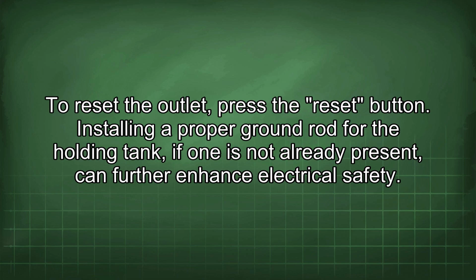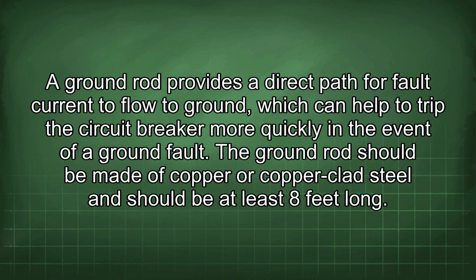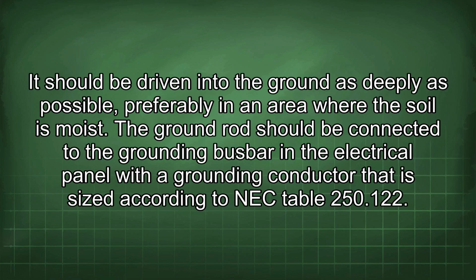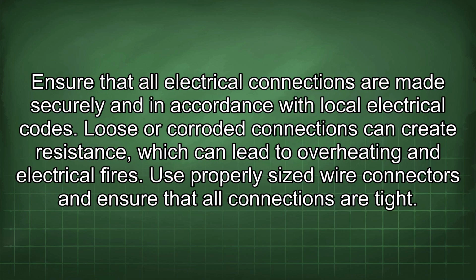Installing a proper ground rod for the holding tank, if one is not already present, can further enhance electrical safety. A ground rod provides a direct path for fault current to flow to ground, which can help to trip the circuit breaker more quickly in the event of a ground fault. The ground rod should be made of copper or copper-clad steel and should be at least 8 feet long. It should be driven into the ground as deeply as possible, preferably in an area where the soil is moist. The ground rod should be connected to the grounding busbar in the electrical panel with a grounding conductor that is sized according to NEC Table 250.122. Ensure that all electrical connections are made securely and in accordance with local electrical codes.